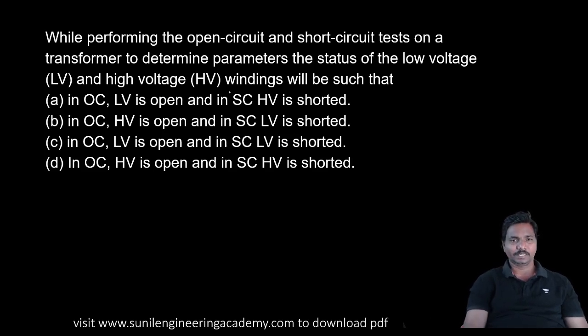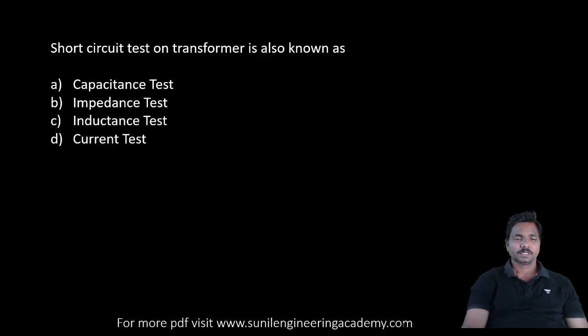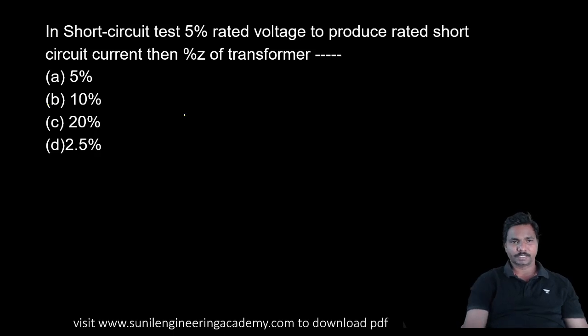Again the same question, but here they are combining both. In case of open circuit, HV is open. Two options are correct. Short circuit test, LV is shorted, not HV shorted. So the answer is option B. We have already discussed this. The short circuit test on a transformer is also known as the impedance test.